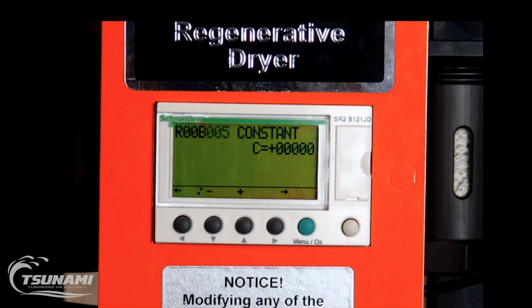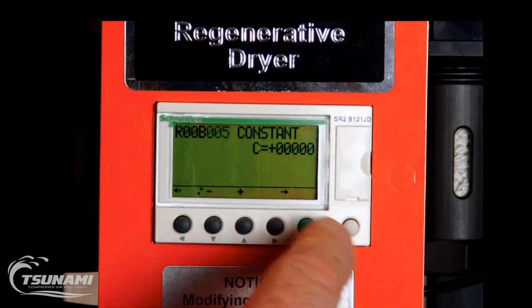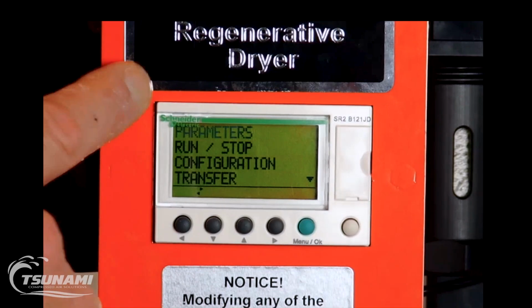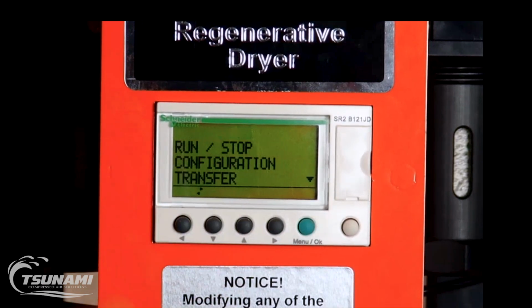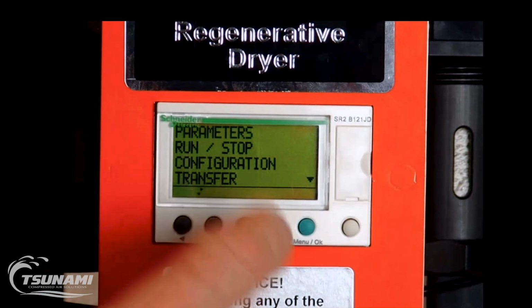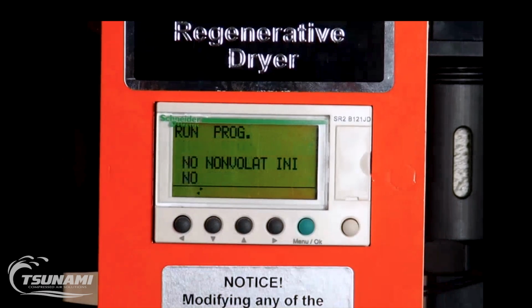So as a standard configuration, this dryer is plug and play. We plumb it in, we plug it in, and it is going to operate as it's set up. If you add a transducer or a digital signal, we then have to start adjusting blocks 4 and 5 to make those accommodations. So we're going to leave well enough alone. I'm just going to hit the menu OK button. It goes back to the parameters, run stop. I'm going to hit the arrow down to run stop, hit OK.